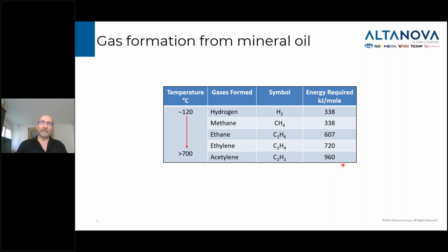So if there's a very high level of those gases, and if you have a spark, well, then that's usually what you will see: a catastrophic failure of your transformers. So this is one of the reasons why acetylene especially is a gas that we look at very carefully, and it often tells you that you have a major fault, because at over 700 degrees, usually it's an arcing problem.